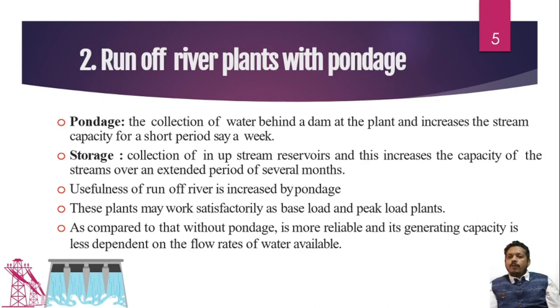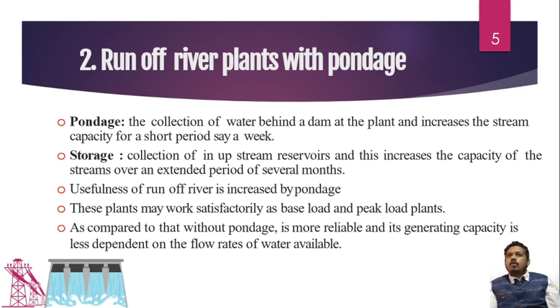In the second type, we add pondage to the run-of-river power plant. The advantage is we can increase the capacity with some storage consideration. If we have pondage for seven to eight hours, even when flow is reduced, we can still use the plant for that limited time. With pondage providing small storage, we can run for fixed defined hours. With a larger storage backup, we can increase firm capacity and use it as base load or peak load.